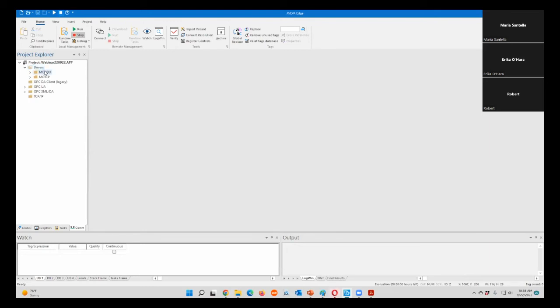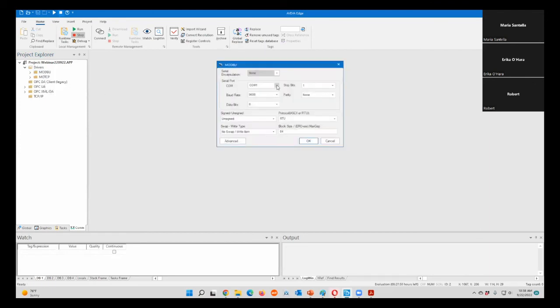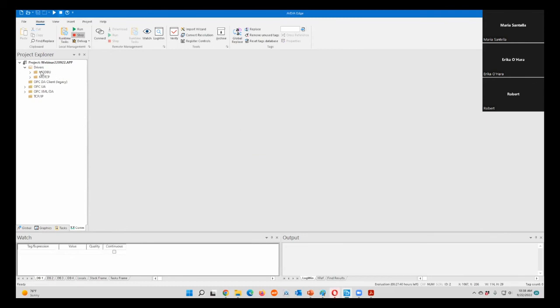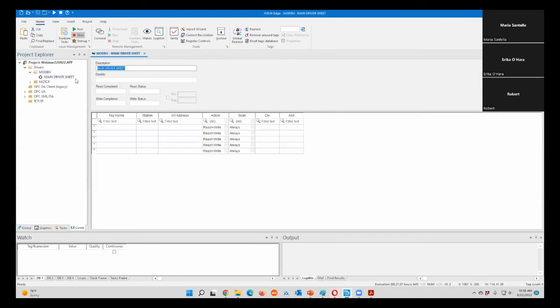The first thing you must do with Modbus RTU is create your connection to the device. I want to again note that the previous slide showed COM4, 9600, N, 1 as our communication settings. So we click OK there. Then we need to edit the main driver sheet. This is where we create our tags, create our association between the data at the PLC, and create a tag within the SCADA system to view and manipulate the data.